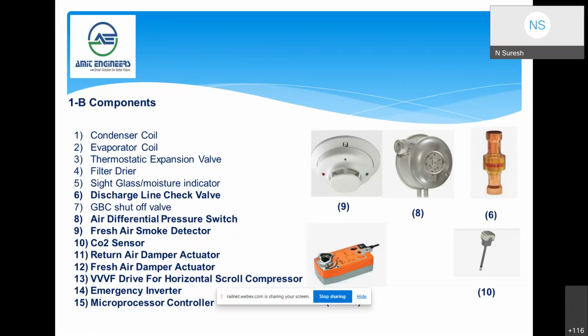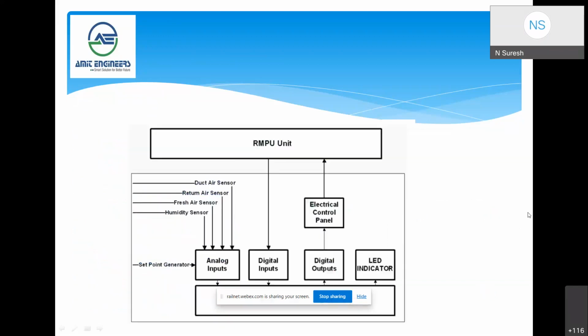These are all proven system components, like discharge check valve, air pressure differential switch, fresh air smoke detectors, CO2 sensors, return air dampers, horizontal compressor, emergency inverter, and microcontroller. This is how it is integrated between the microprocessor controller, the switchboard cabinet, and the RMPU. This is a schematic of how it is integrated between all these three components.